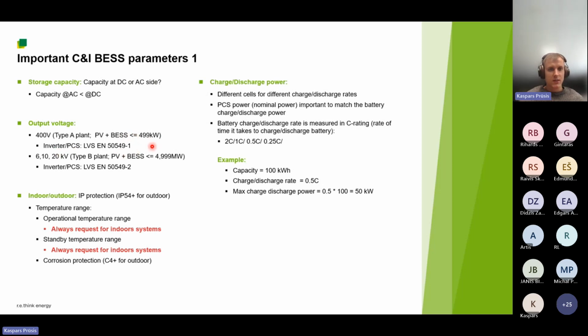And in this case, if it's type A plant, then inverter or power conversion system should comply with LVS EN 50549-1 standard, which is low voltage standard. And if our system is more than 4.999 megawatts of power, then of course that's type B power plant, and we must connect this system to 6, 10, or 20 kV lines, and usually this will happen using medium voltage transformers. And in this case, we have to comply with medium voltage standard, which is 50549-2.